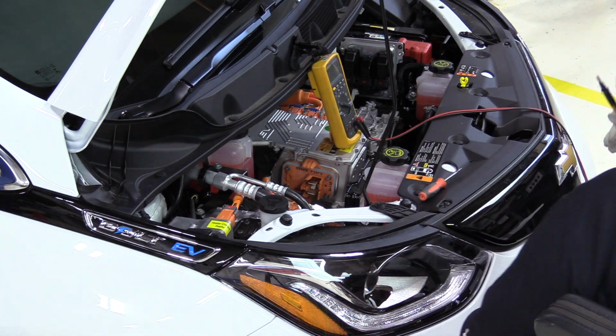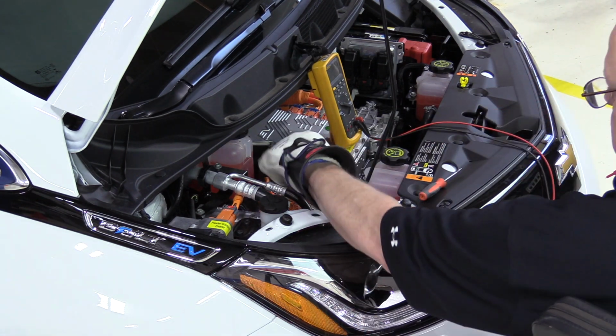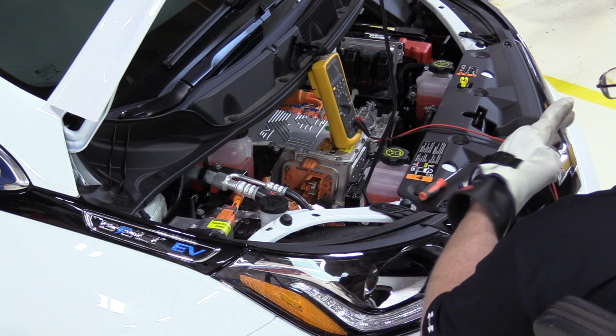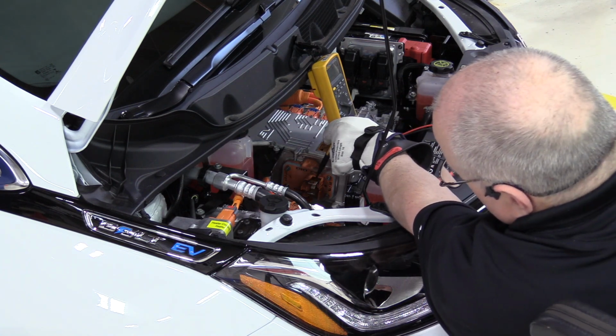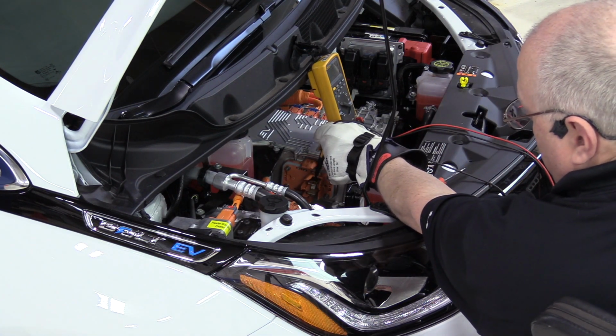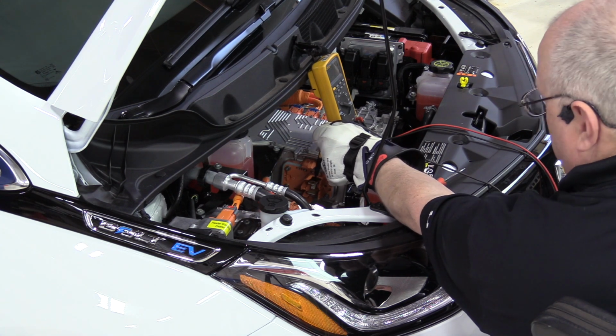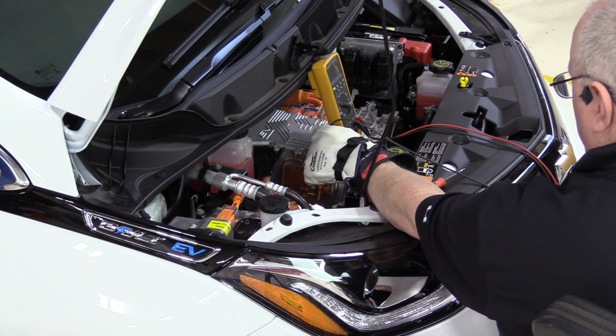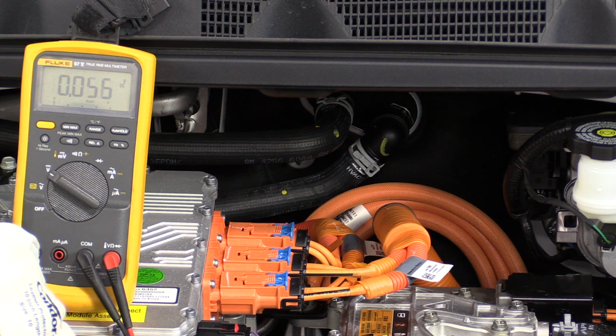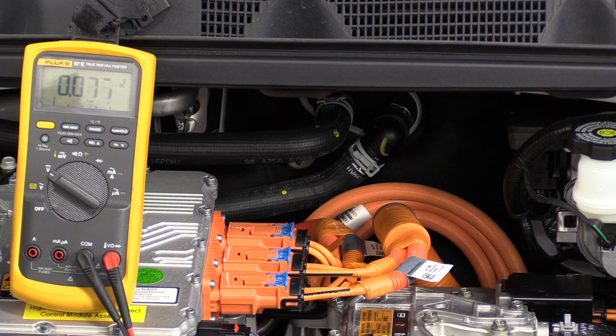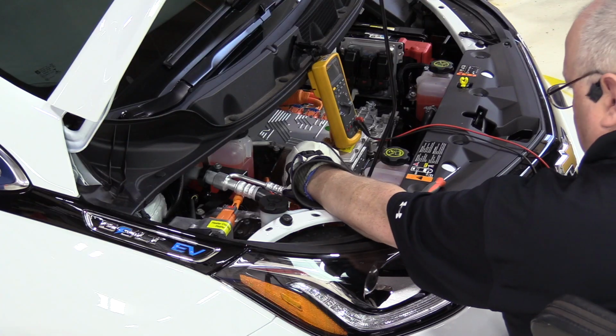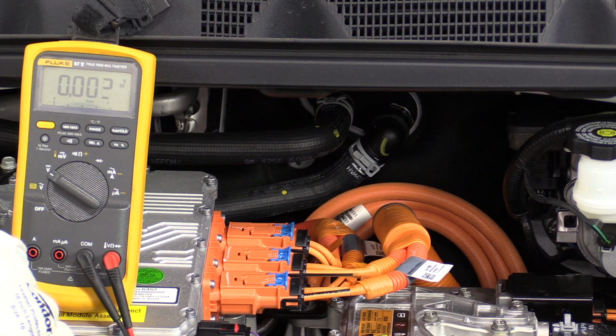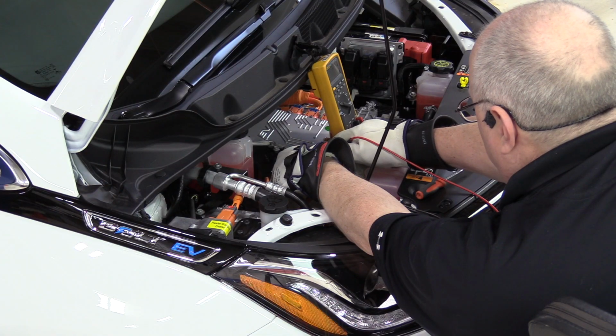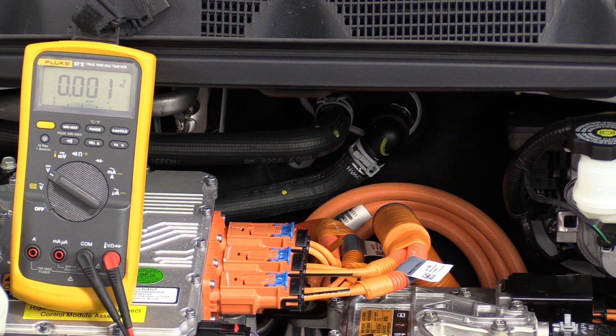So let's take some measurements here. There are 3 measurements we're supposed to take. We're supposed to check each of the 2 electrical terminals here to ground, chassis ground. I'm reading 30 millivolts on that one and dropping, and the one down below 0 volts, and then the 2 terminals together 0 volts.